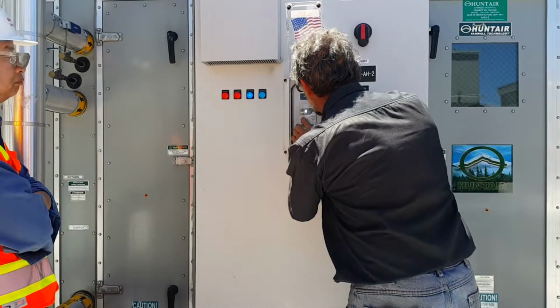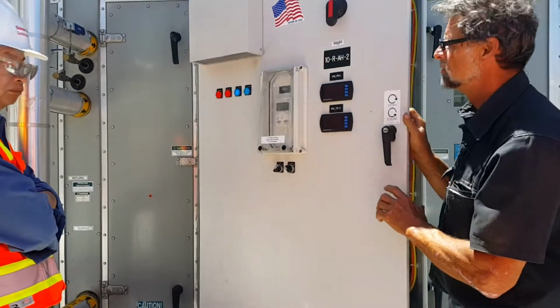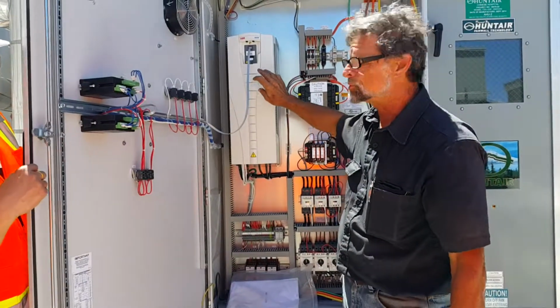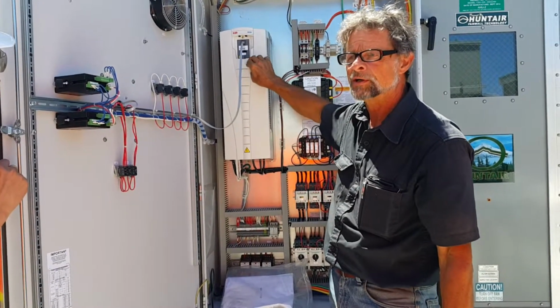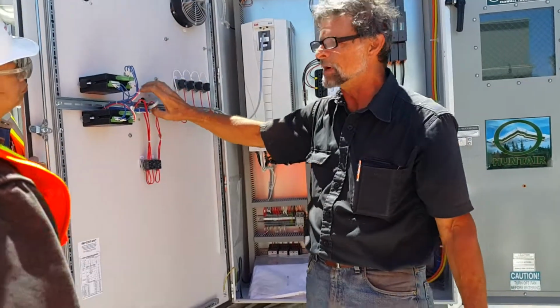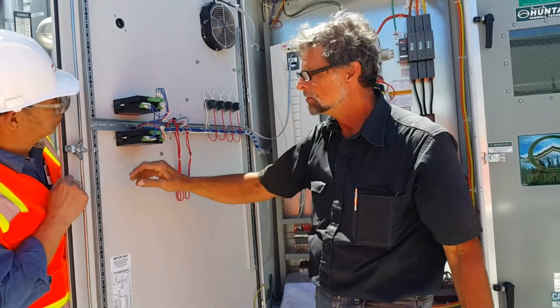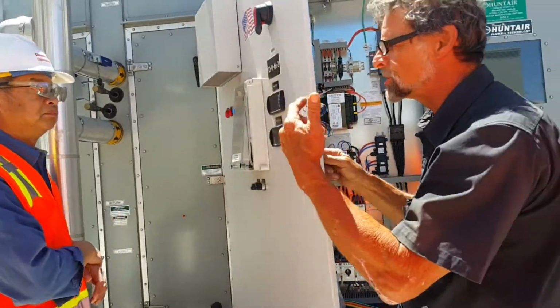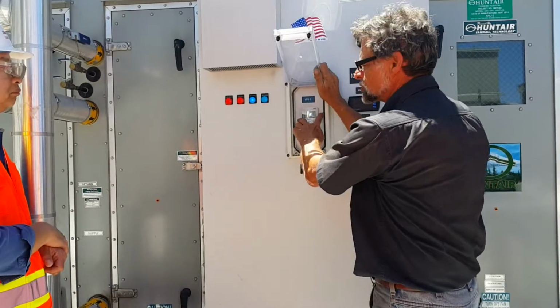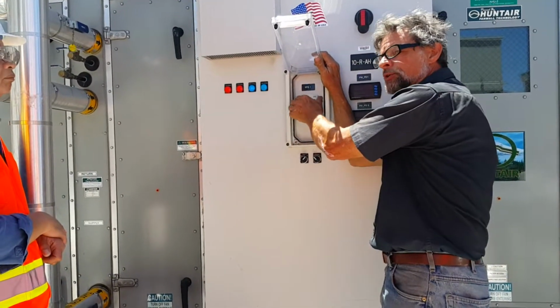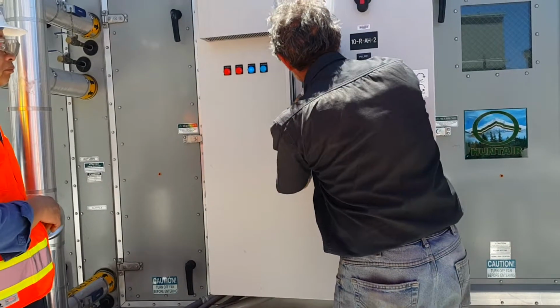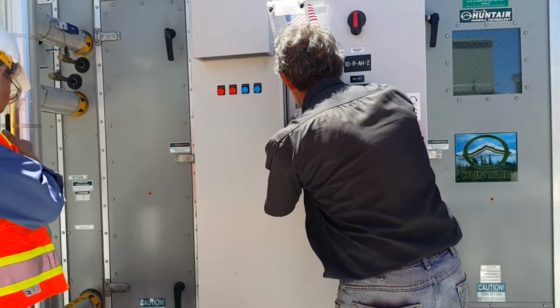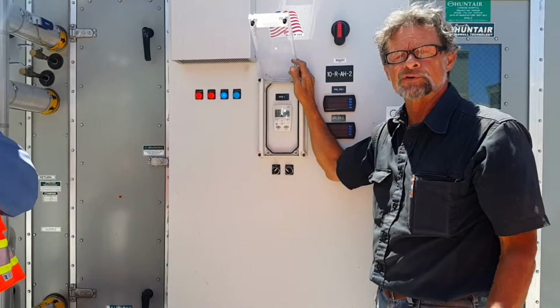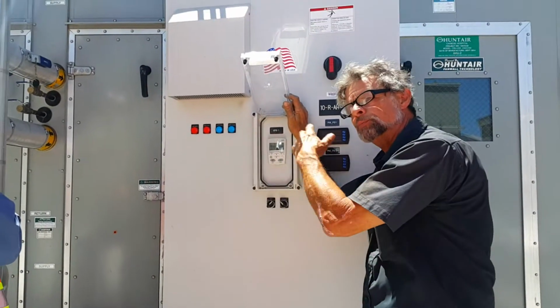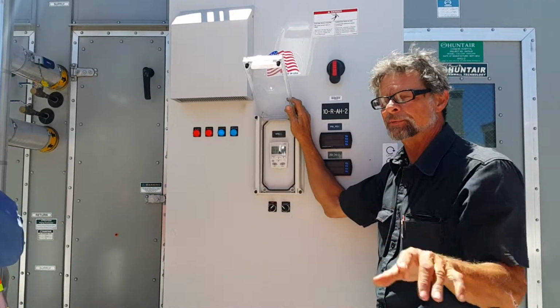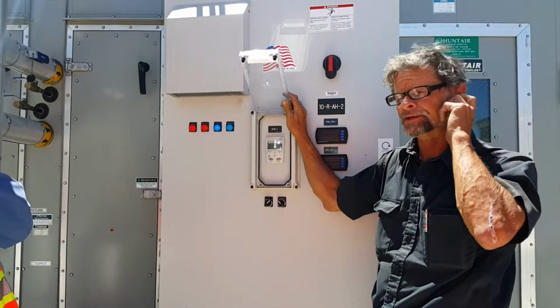What we just did was we took everything about the way the drive is set up that's programmed in here, and we put it in a memory spot in here. So if the drive ever blows up and you change the whole drive, you can put this same panel back here. The new drive will come with a new panel, but use the old panel. You go back to parameter backup, and you hit download full set. It'll take everything that was in that memory and put it back in the drive. That way you don't have to mess around trying to figure out everything that it needs to be programmed.